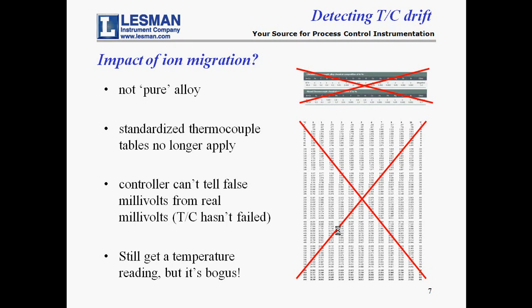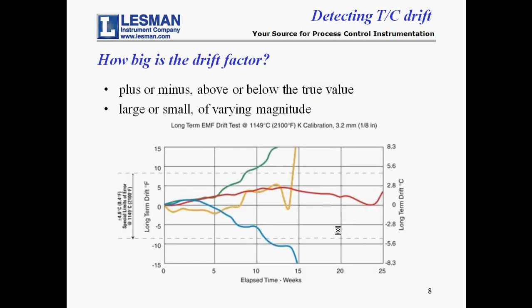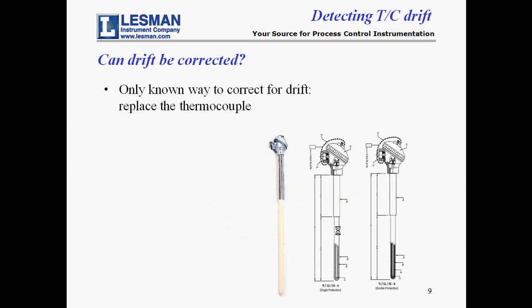Impure alloys produce a millivolt output that does not correspond to the values in the published standardized table. The problem is that the temperature controller interprets the millivolt electrical signal according to the published tables, but a millivolt output from a polluted junction has no published table. The result? Drift. Temperature readings from a drifting thermocouple are not true temperature readings — they're bogus temperature readings. Drift can be plus or minus above or below the true value; the green curve drifts upward and the blue curve drifts downward. The magnitude of the drift can be large or small. There is no known way to correct for drift other than replacing the sensor with a new thermocouple made from pure alloy.